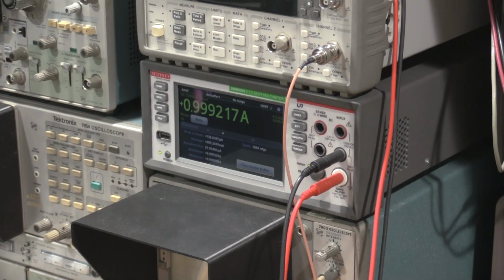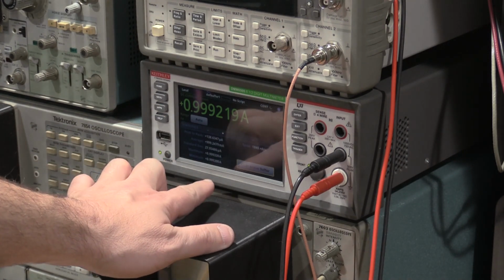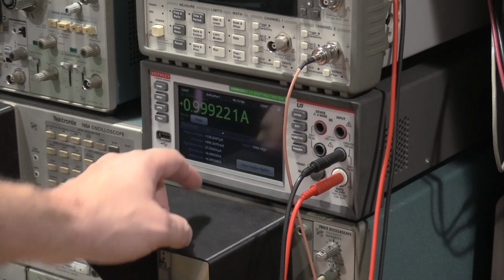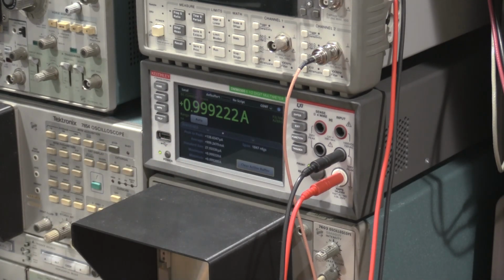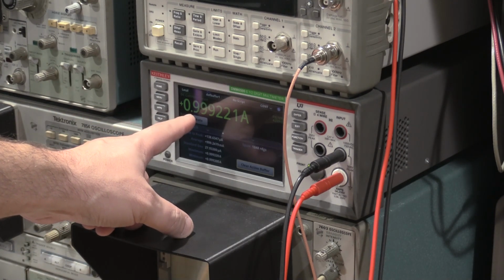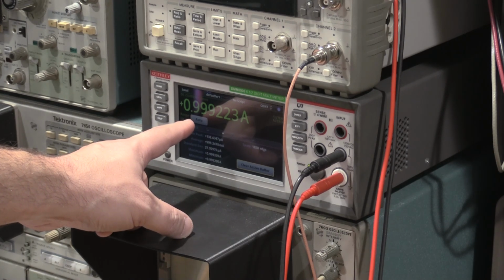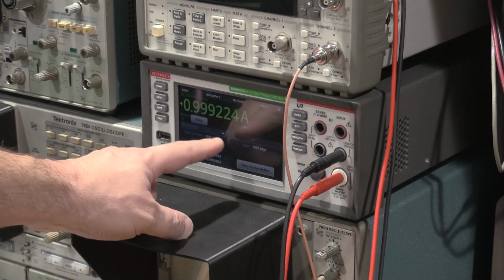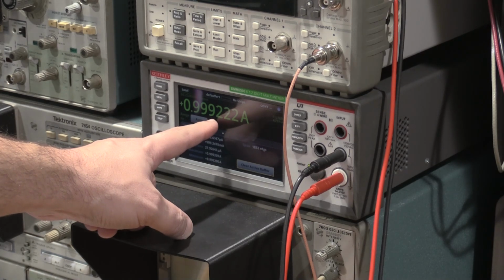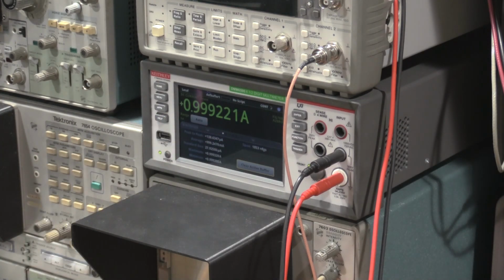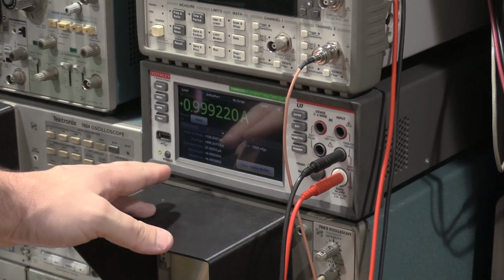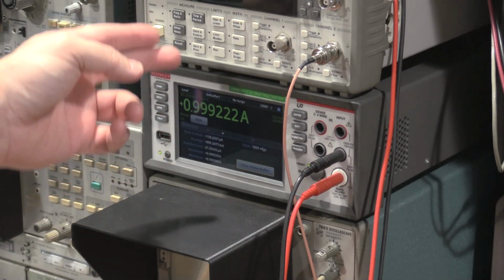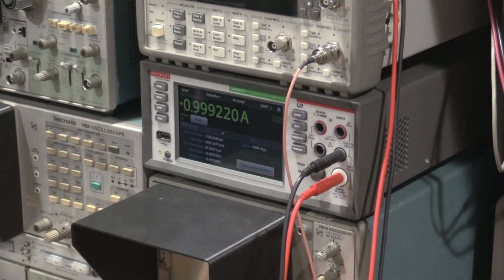Okay, so I've let the unit warm up for a while and run. And according to this meter, the unit's out of spec. However, that could also be this meter, because the accuracy specification for the 1 amp range is plus or minus 0.01% plus or minus 400 microamps. So that should be 9999, with a bare minimum of 9995, taking into account the lowest of its tolerance. So this is measuring it out of specification, but that could also be the tolerance of the 6500. So I really need to check this on the 7510.